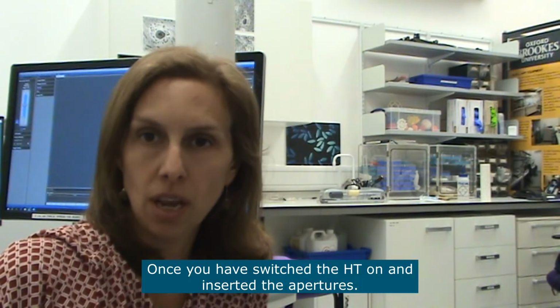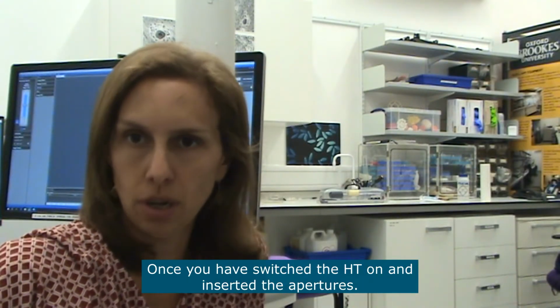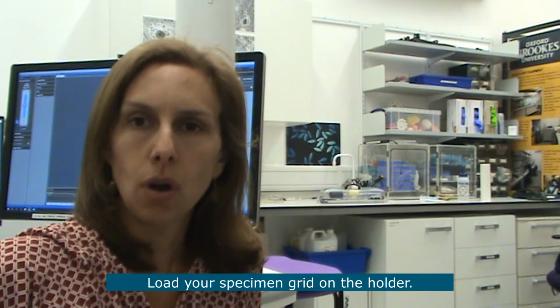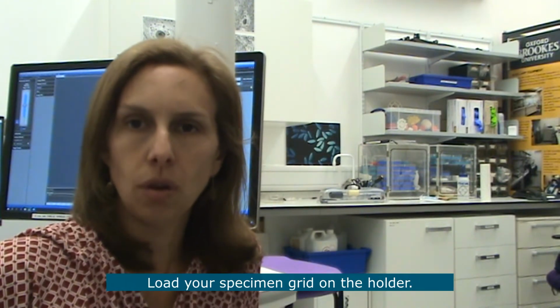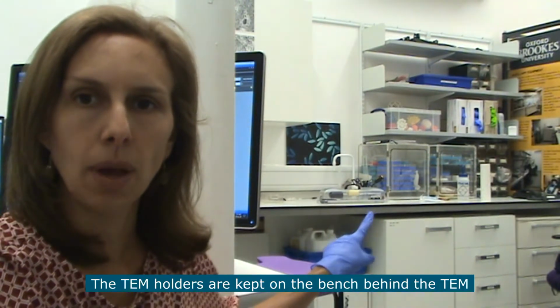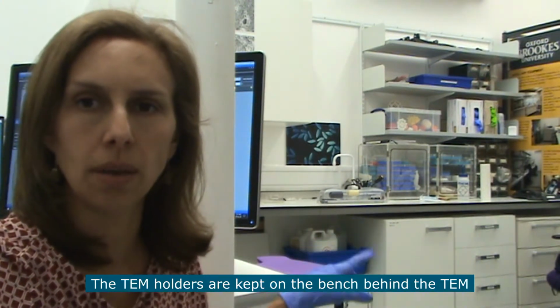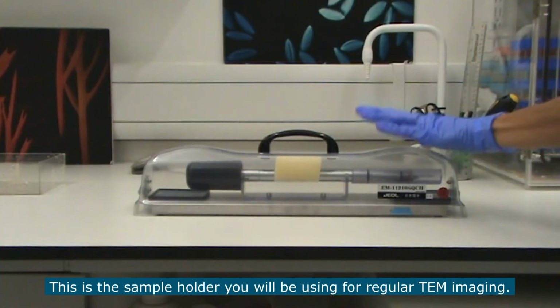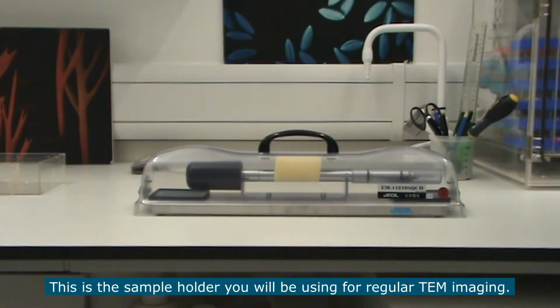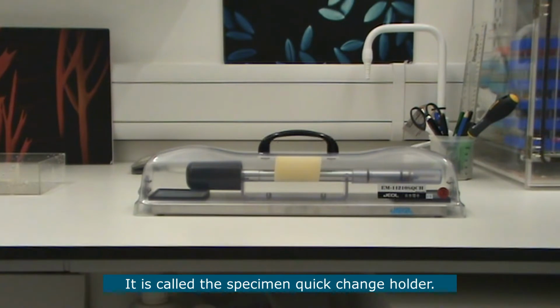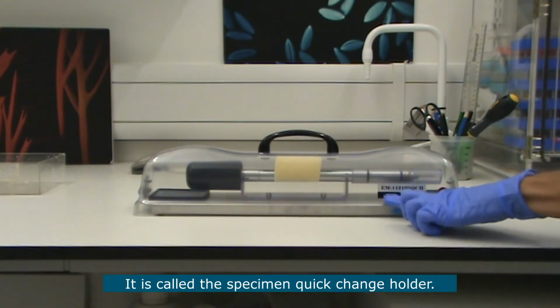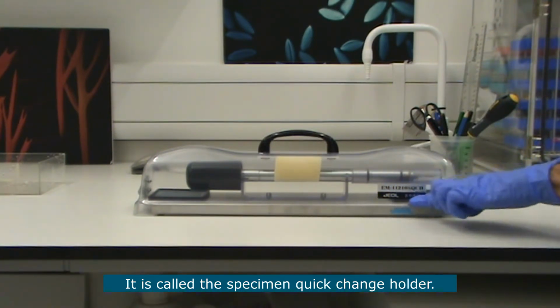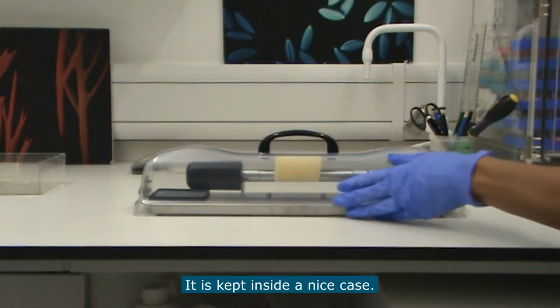Once you've switched the HT on and inserted the apertures, you should put your specimen grid onto the specimen holder. All the holders are kept behind the microscope on this bench here. This is the sample holder you'll be using for regular TEM imaging. It's called the quick change holder, and that's its name down here. It's kept inside a nice case.